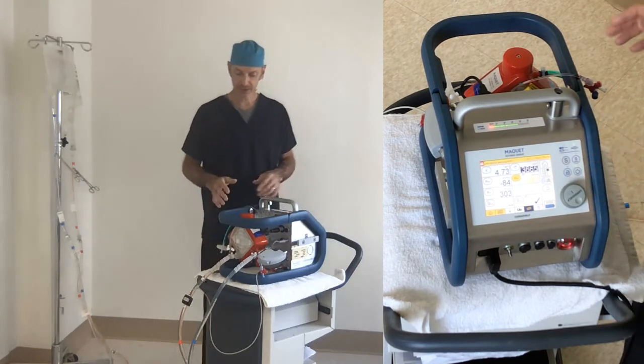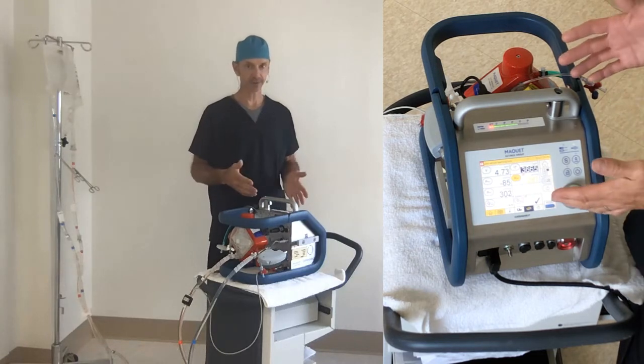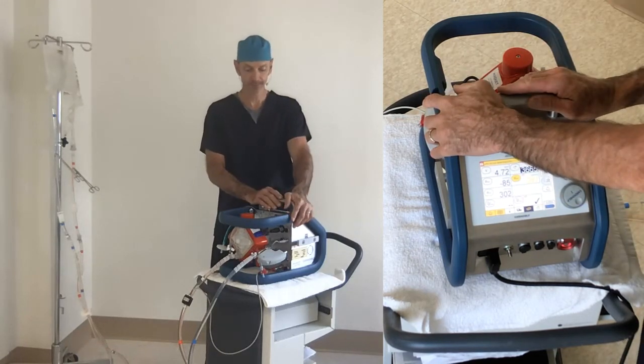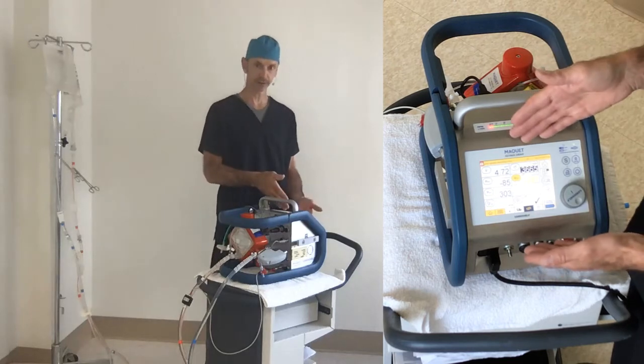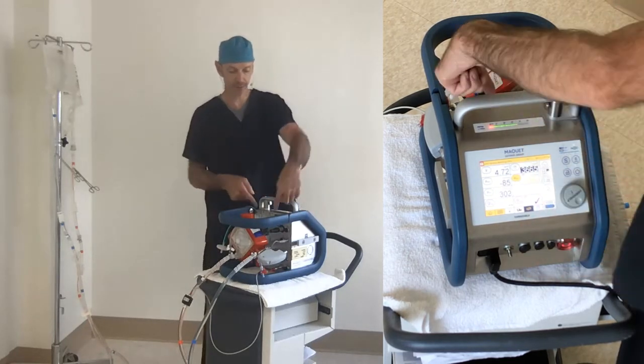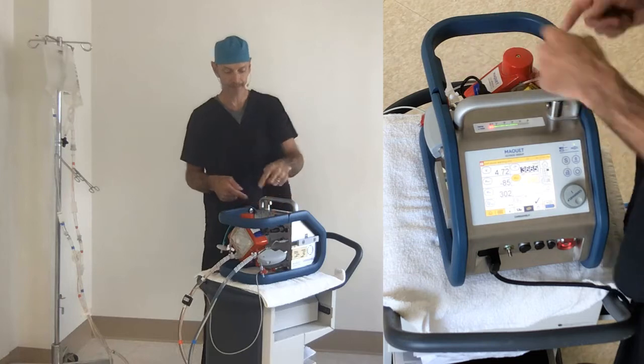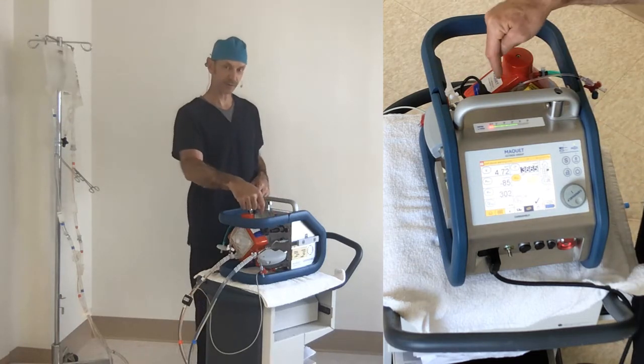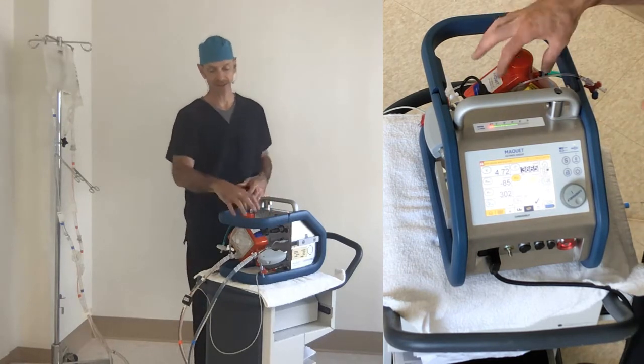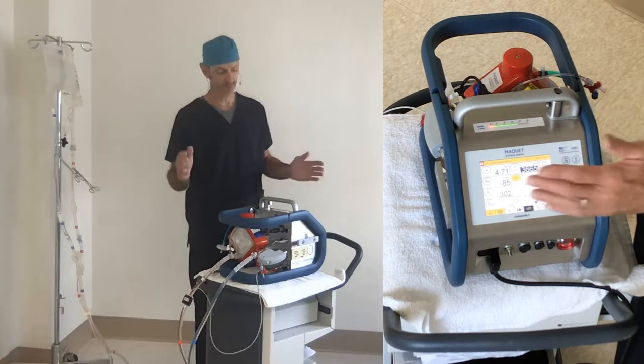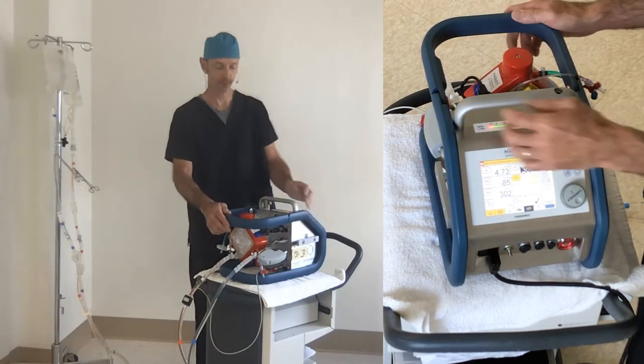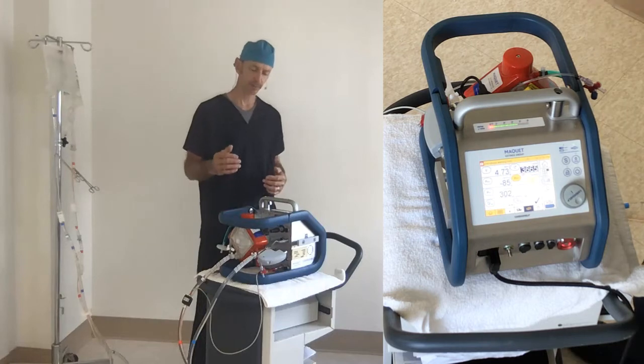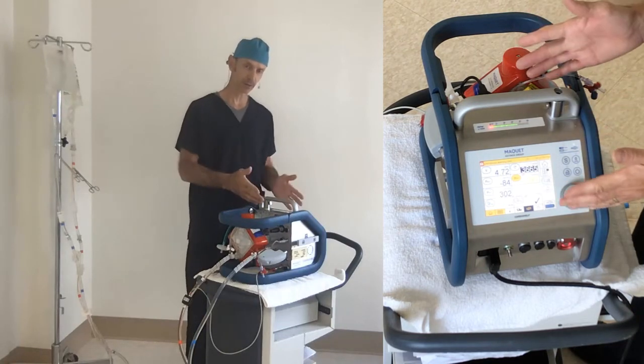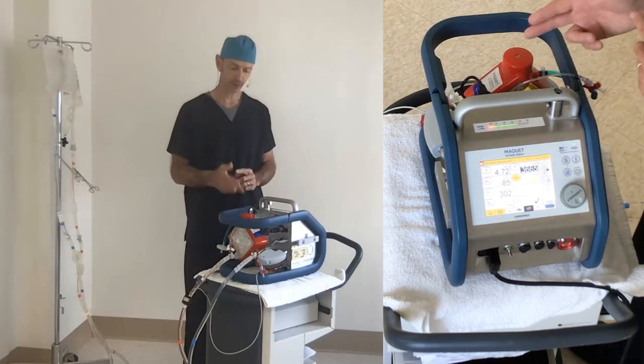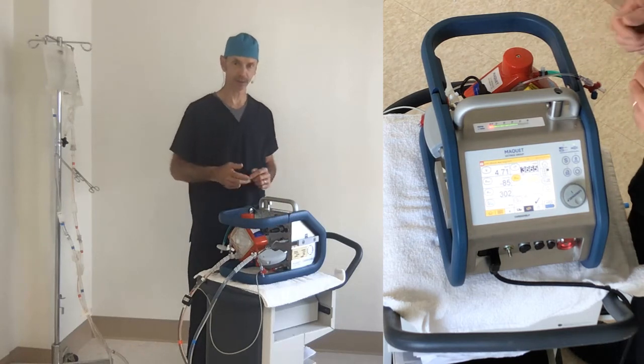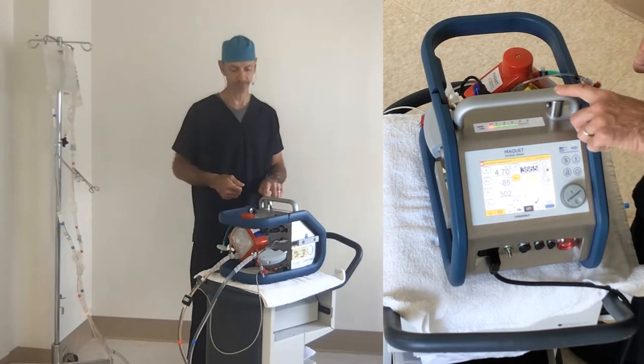So if anything other than bubbles and pressure stop this thing, it's probably something that you need a new console for. If the brain fails, the pump might stop. If the motor fails, the pump might stop. If the disposable pump fails, well then you need a whole new circuit, and you get to keep the hardware. But we're practicing pump failures that are electronic in nature, and we're going to jump the pump to a hand crank, and then we're going to change out the console.